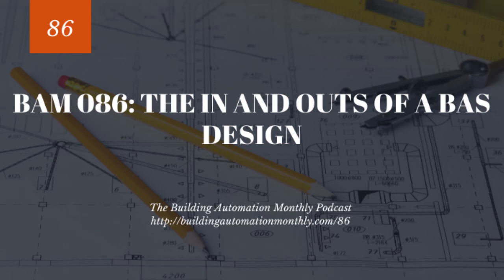And then finally, you have a bill of materials, which is on every system drawing. You'll have a bill of materials, and typically on your network riser as well. And for your bill of materials, you'll want to keep that in an Excel sheet and keep all of the materials on a single tab. That way you have an entire look at everything you should purchase. Otherwise, you're going to end up purchasing duplicate stuff. That's how I see jobs get out of budget, because they order the wrong stuff and it gets all mixed up because you've got bill of material overlap, especially since you're often doing your design over several days and you may forget what you put on one bill of materials.